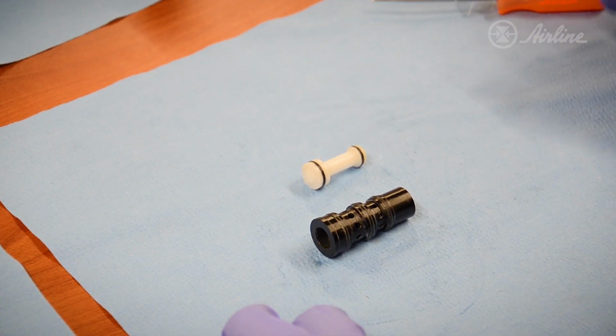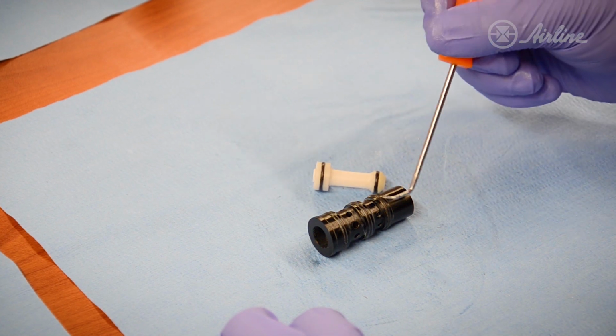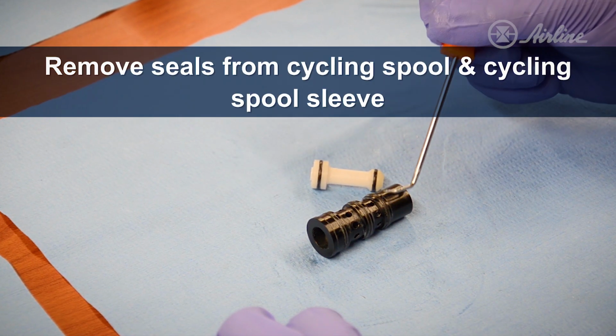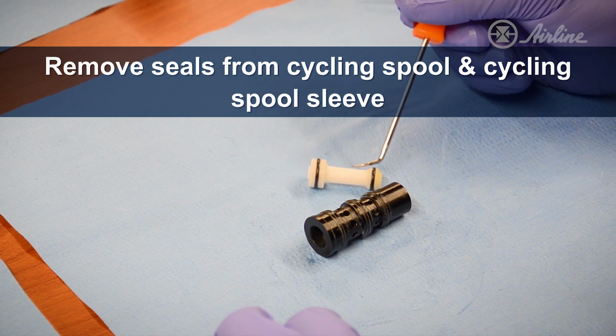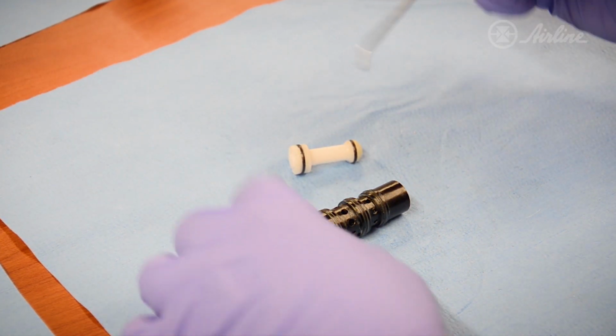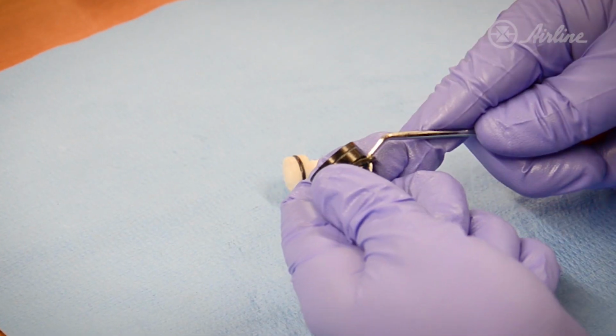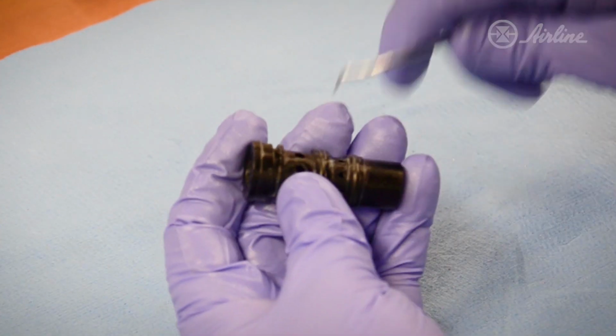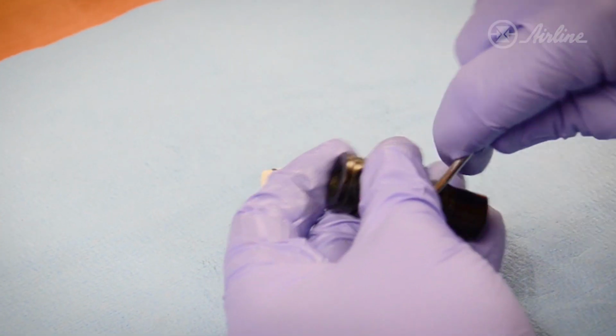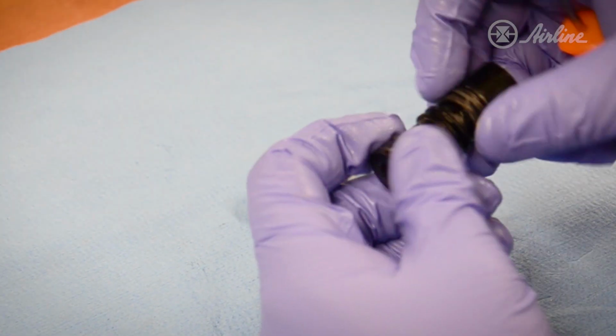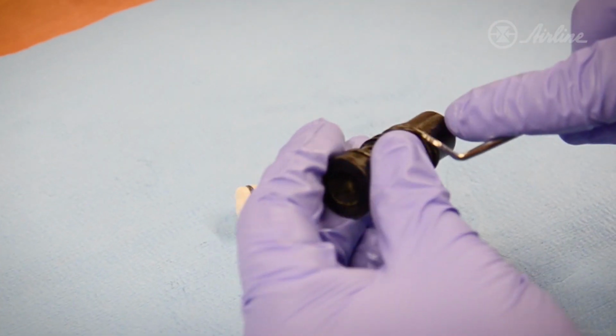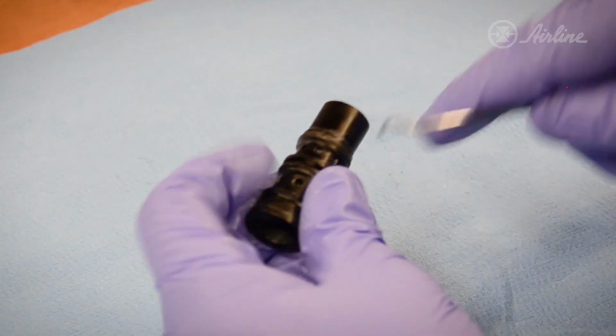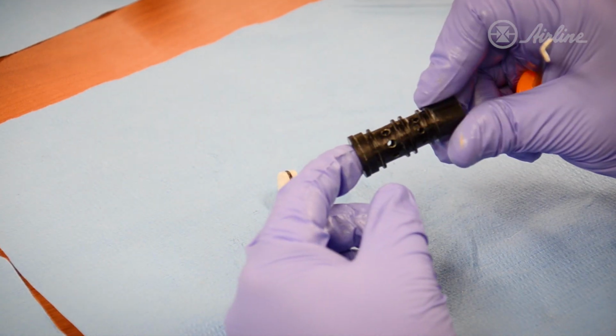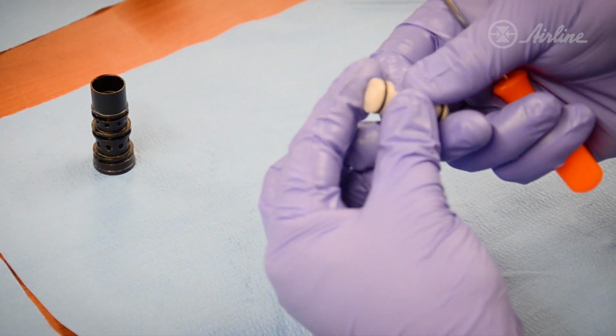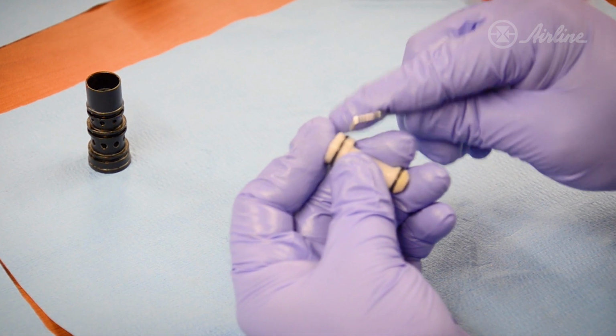Now we'll reseal the cycling spool and the cycling spool sleeve. There's 3 O-rings that need to be removed on the spool sleeve and 2 O-rings that need to be removed on the spool itself. We'll use a pick to carefully remove these O-rings. So we've removed all 3 O-rings from the cycling spool sleeve, and we'll remove the 2 O-rings from the cycling spool itself.